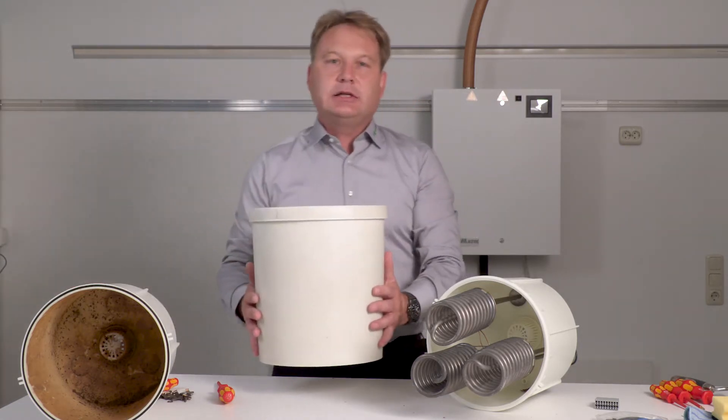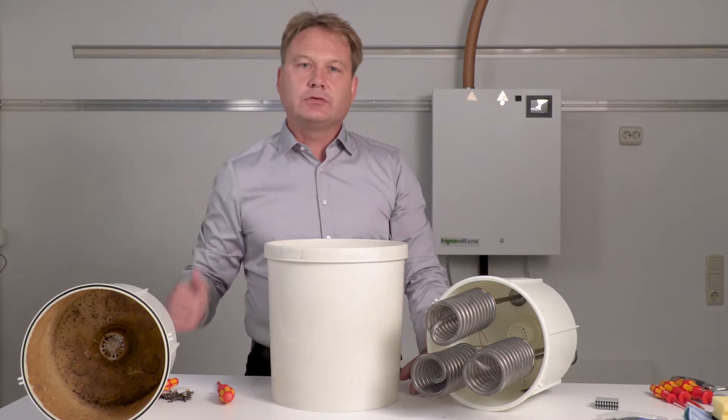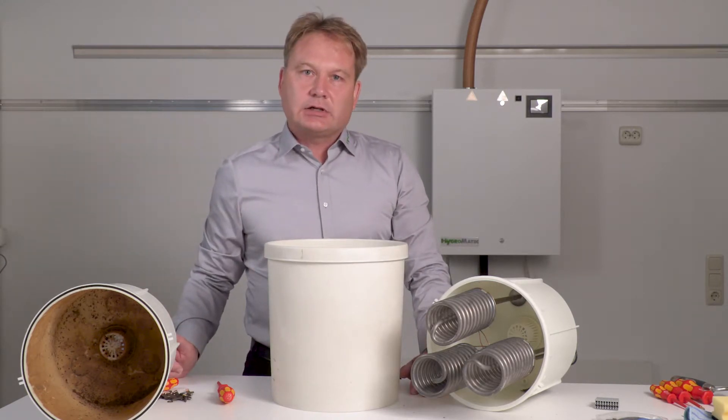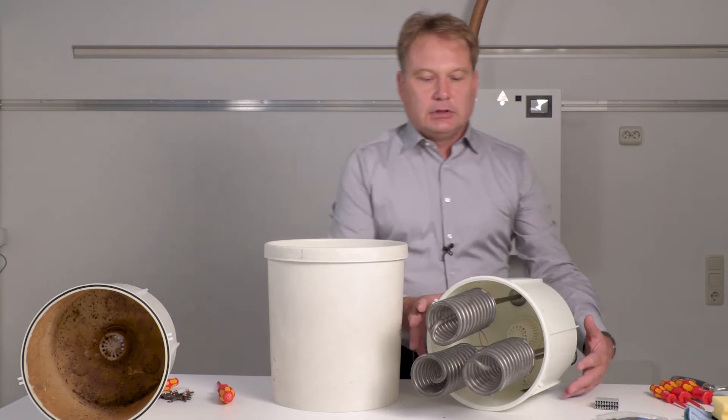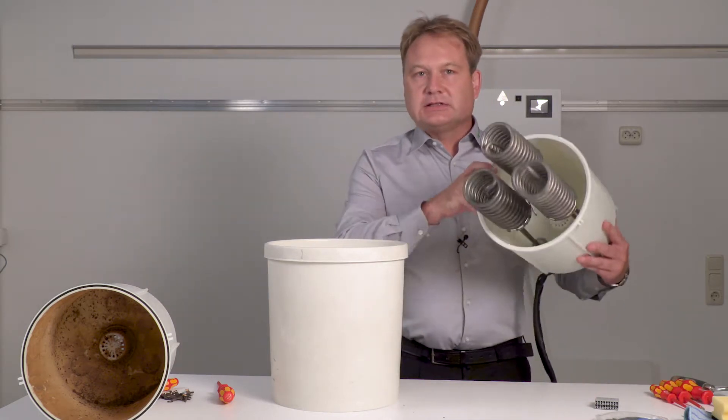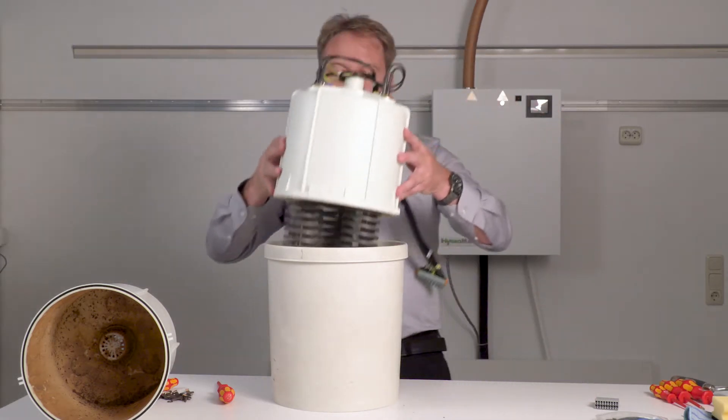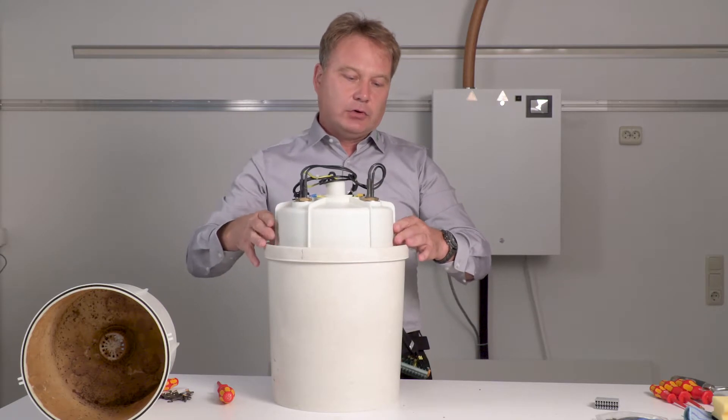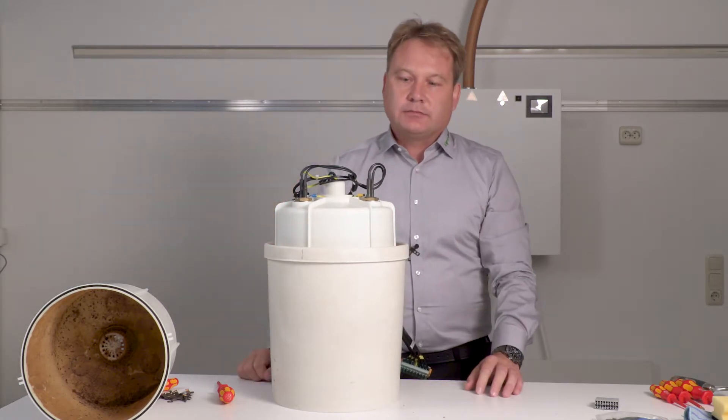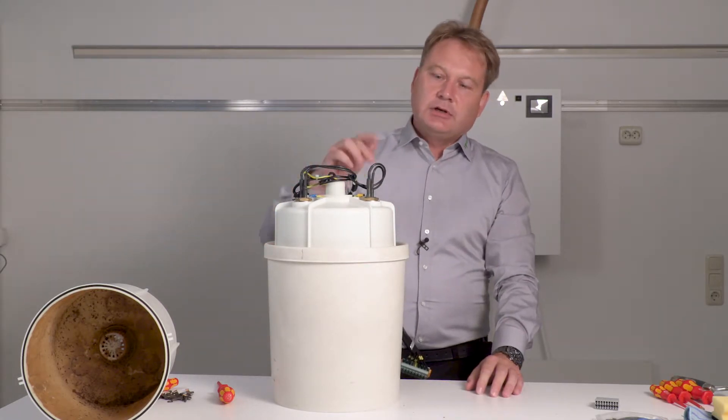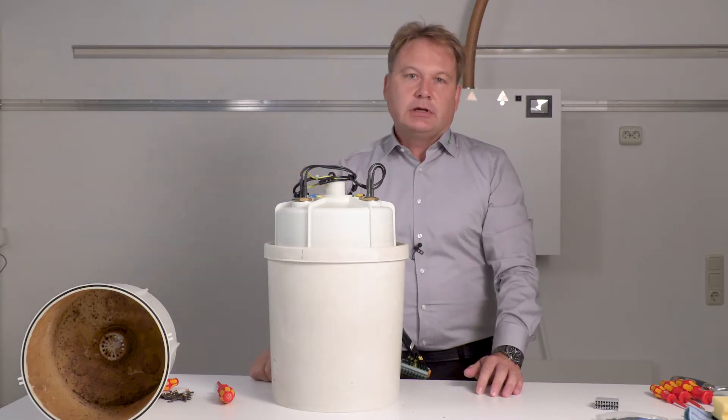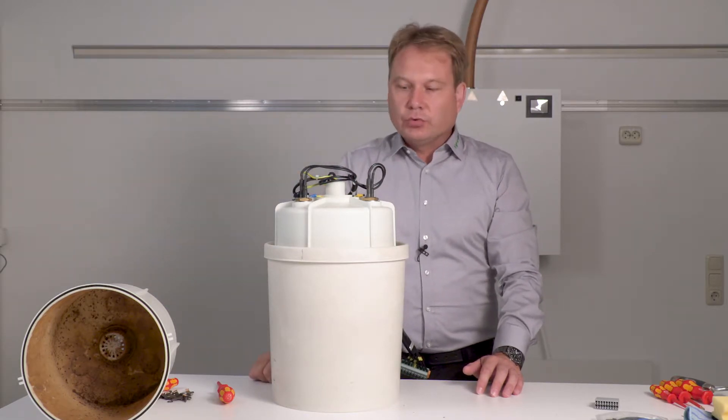You can take a container, mix your citric acid or descaling agent here, and place the upper half of the steam cylinder into it and let it descale. Please make sure that the connectors from the heater element do not come into contact with water or acid.